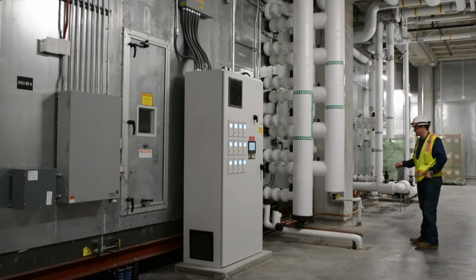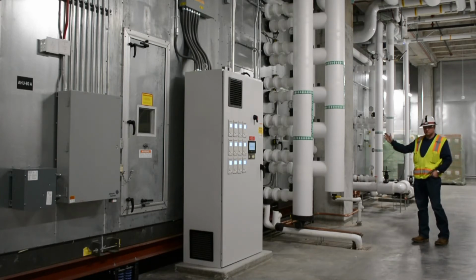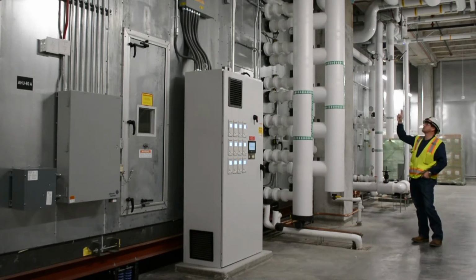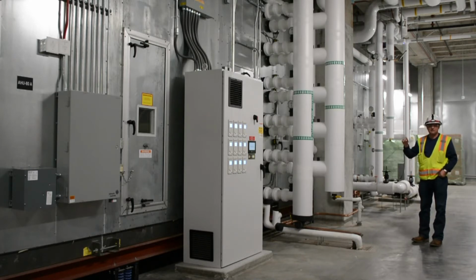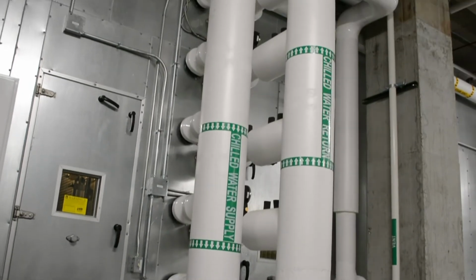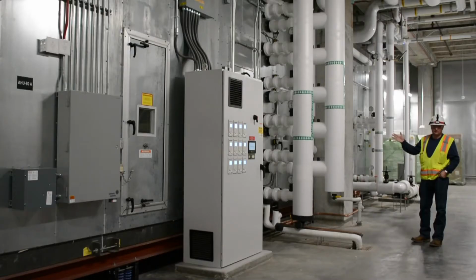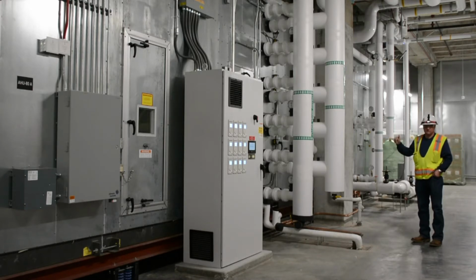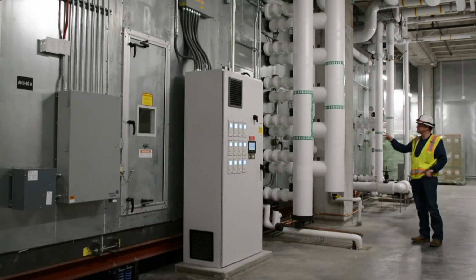The next section for this air handler has our humidifier. The humidifier valve modulates to maintain discharge air humidity set point, and it's sized obviously appropriately for 100% outside air. So in the winter months when we're below 20 degrees outside, you should see quite a bit of humidity coming off of this machine right here in this section, and that's normal.